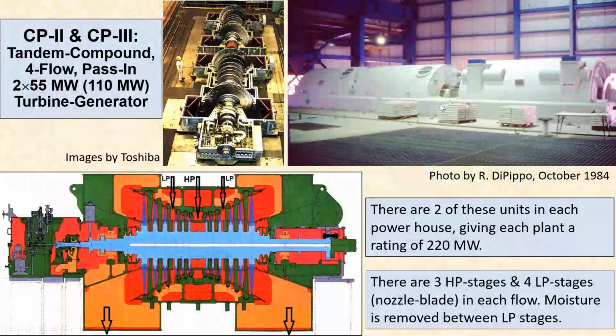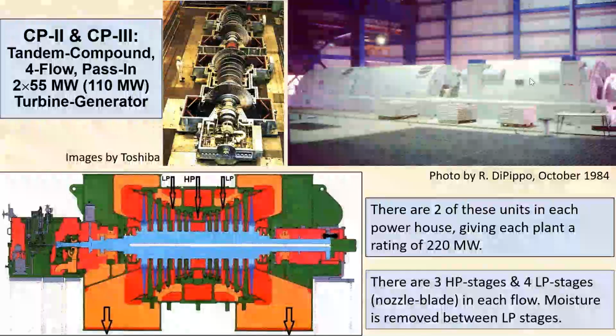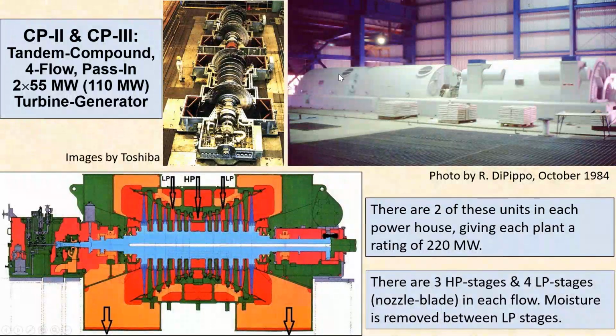And just a photograph inside the unit. I took this one in 1984. The unit had just come online. This is the generator, 110 megawatts. These are 2 55 megawatt double flow turbines. Here it is on the test stand in Japan. And this is a cross section of the turbine with the high pressure coming into the middle section, and then the low pressure steam mixing with that and going through the rest of the turbine and out. There are moisture removal sections to remove some moisture, which prevents erosion of the turbine. Next.